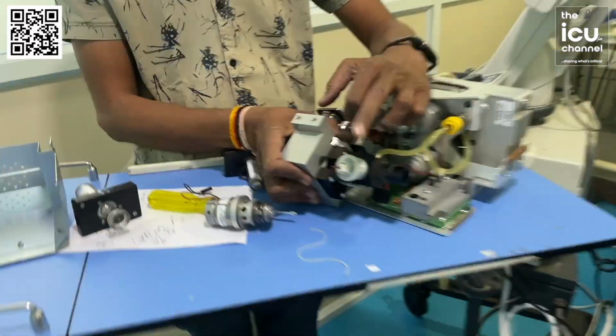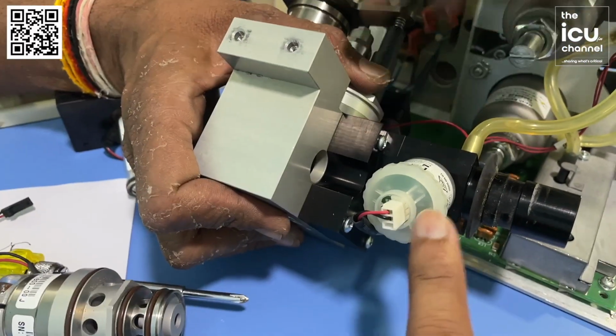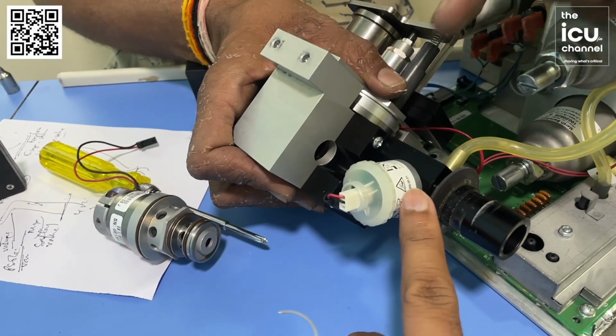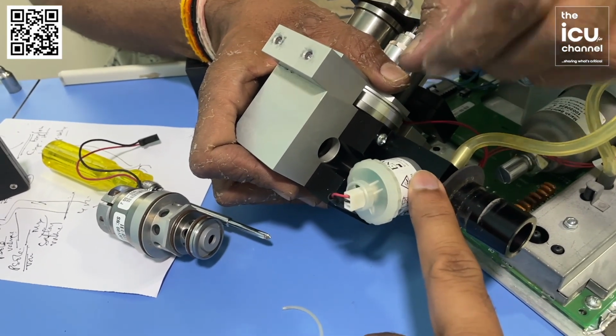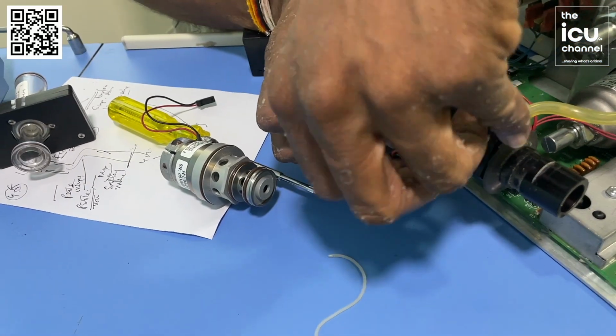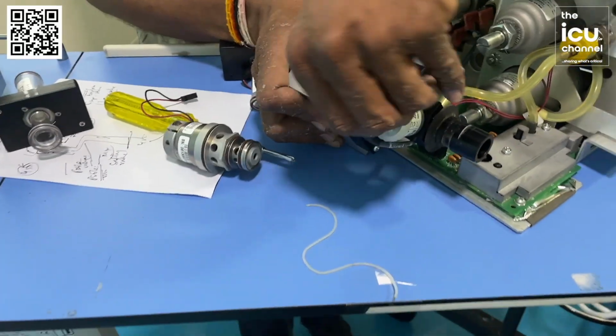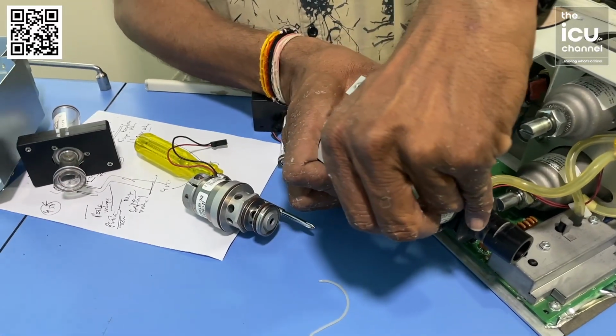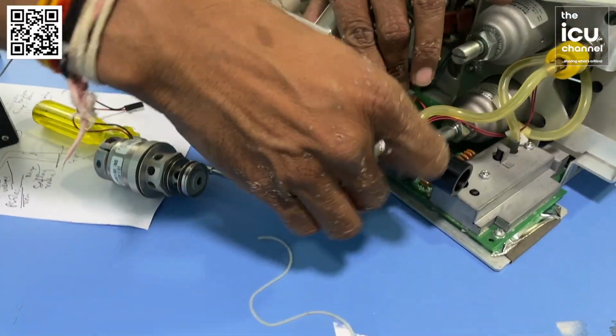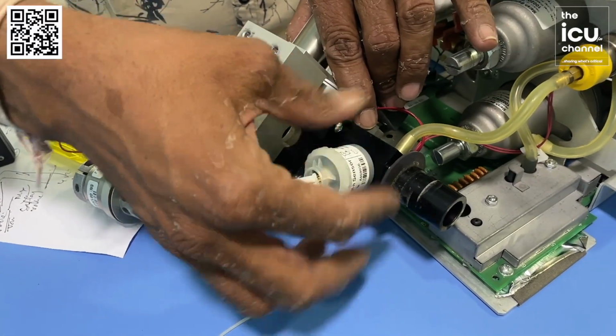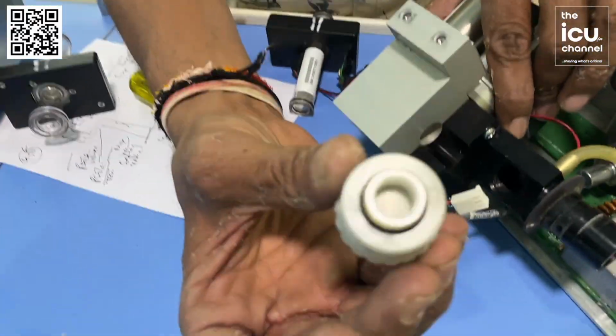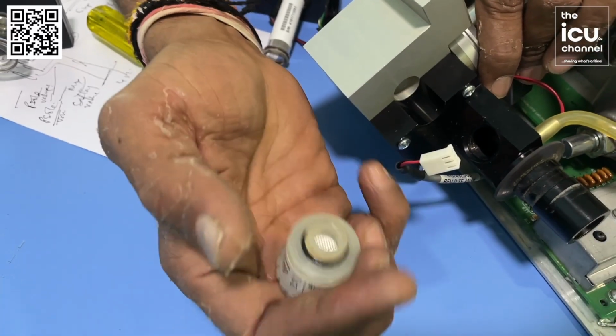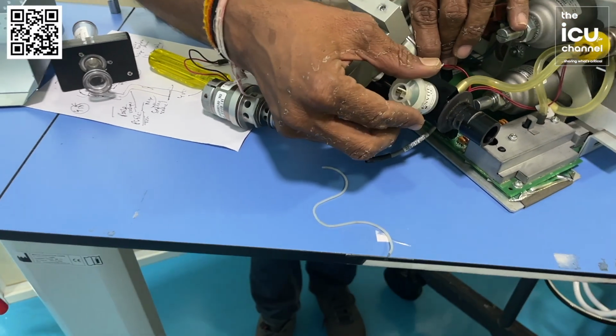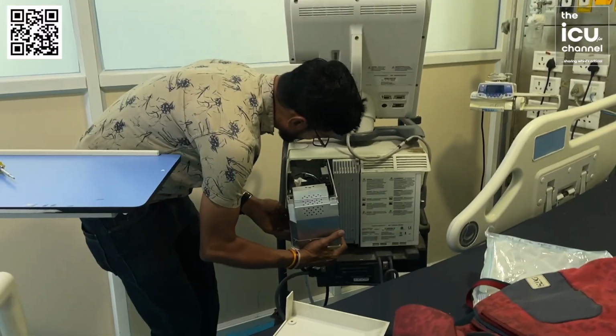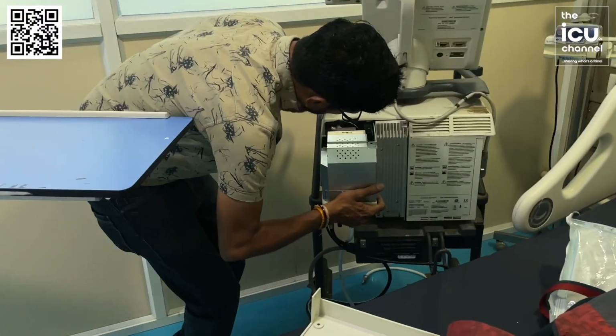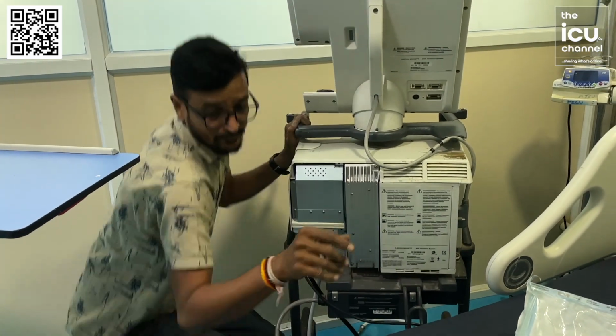Now one more thing which remains here is the oxygen sensor. The purpose of this oxygen sensor is again to check whether the correct amount of FiO2 is being delivered or not. Suppose we have set 40% FiO2, 50% FiO2, so whether we are delivering the correct amount of FiO2 to the patient or not. So this is the oxygen sensor, meaning the FiO2 sensor, technically it should be said. This is small equipment, but very important. You get an alarm for low FiO2 like that; it is because of this sensor. So Pawan is putting the inspiratory kit back inside the ventilator. It's done, and now we'll move to the expiratory side.